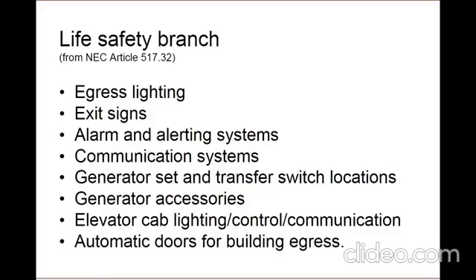So the life safety branch is the most clearly defined branch in NFPA. It lists exactly what is required to be connected to this branch and stipulates that this and only this is what may be connected. It includes the following: egress lighting, exit signs, alarms and alerting systems, which include fire alarms, medical gas alarms, and mechanical control alarms required for effective life safety system operation. This includes communication systems, both illumination and receptacles at generator set and transfer switch locations, and generator set accessories, including fuel pumps, ventilation fans, louvers, controls, cooling systems, basically anything that's going to keep that generator up and running.